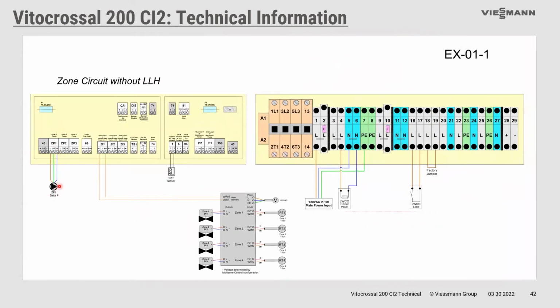There's the pump that's heating the circuit. So that pump there gets a call anytime any of these zones call. So it's going to be an operational pump. Now, depending on how your piping system is, you probably want to make this a delta P pump, because as these zone valves open and close, the head loss across the pump is going to change.